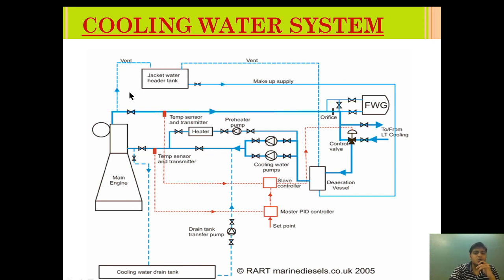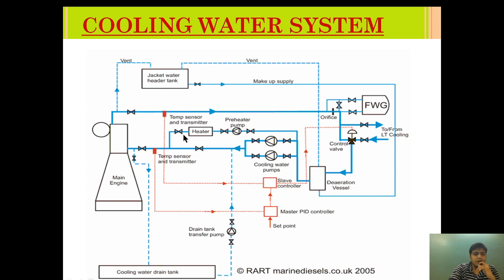This system is called the high temperature cooling circuit, and this pump is called the high temperature cooling pump — the HT system. The LT system provides cooling for the lube oil cooling system, piston cooling system, and also the auxiliary cooling system. The heater here is doing the same thing as in the earlier diagram — maintaining the necessary temperature when the engine is in a standstill condition. A pre-heater pump is provided for circulation. I hope you understand the modified advanced diagram of the cooling water system.